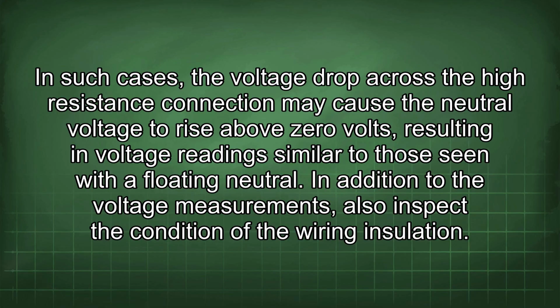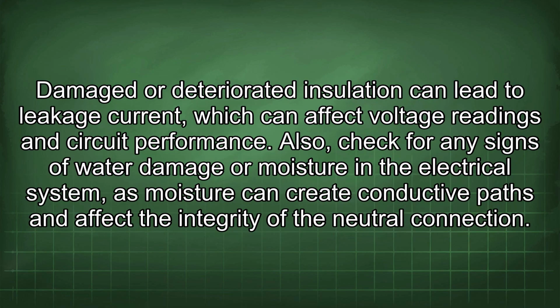In addition to the voltage measurements, also inspect the condition of the wiring insulation. Damaged or deteriorated insulation can lead to leakage current, which can affect voltage readings and circuit performance. Also, check for any signs of water damage or moisture in the electrical system, as moisture can create conductive paths and affect the integrity of the neutral connection.